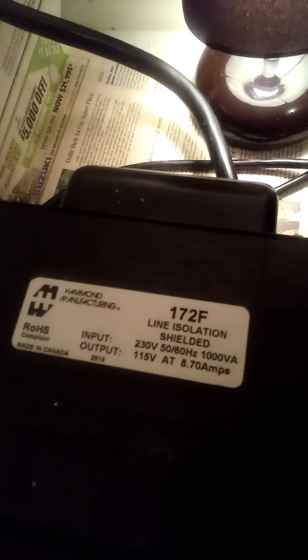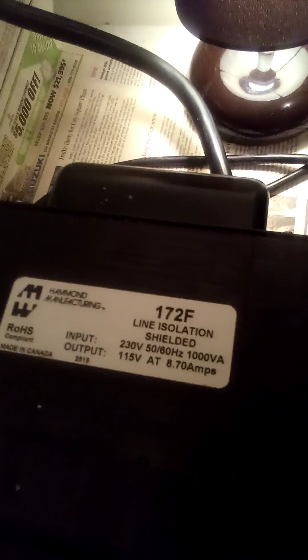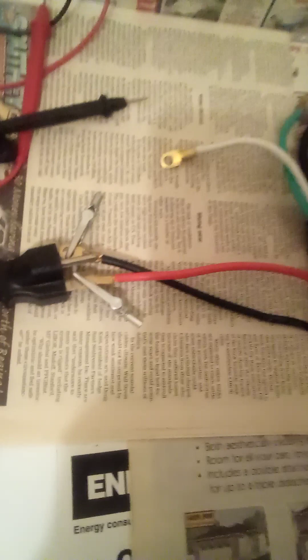It's a 2-to-1 step-down, rated for 230 volts to 115, but I've got a little over 240 volts going into it. And it's running this 25-watt light bulb at 120 volts. So right away I'll make the current measurements to show you the levels, and then I'm going to talk about the problem and solution regarding all step-down transformers.